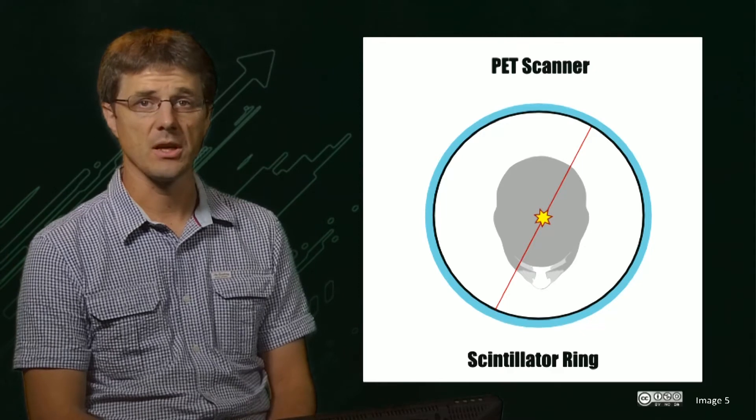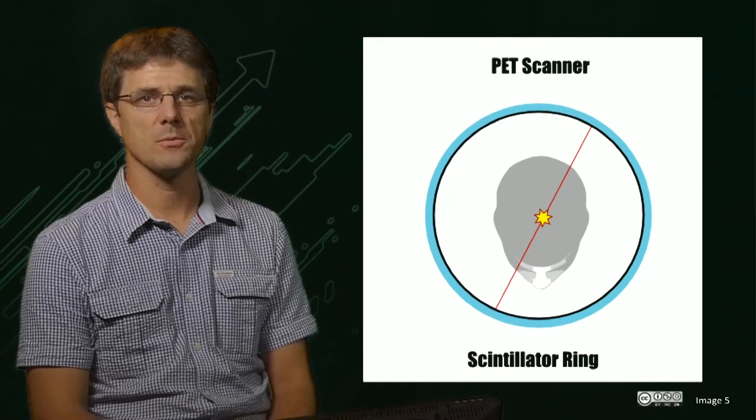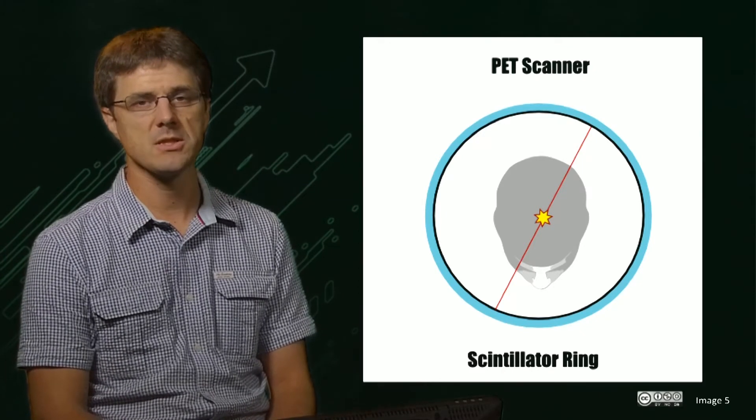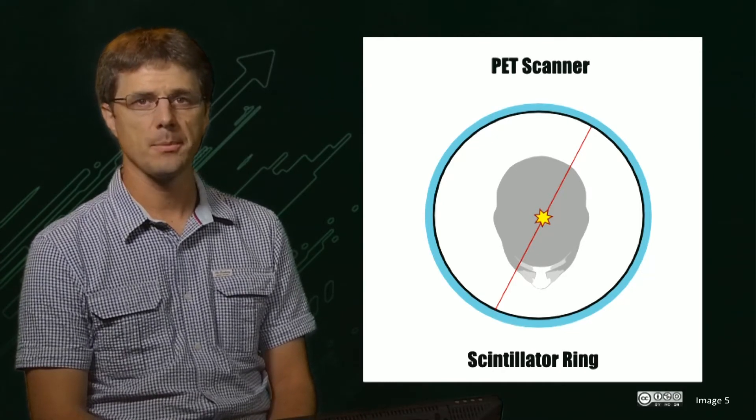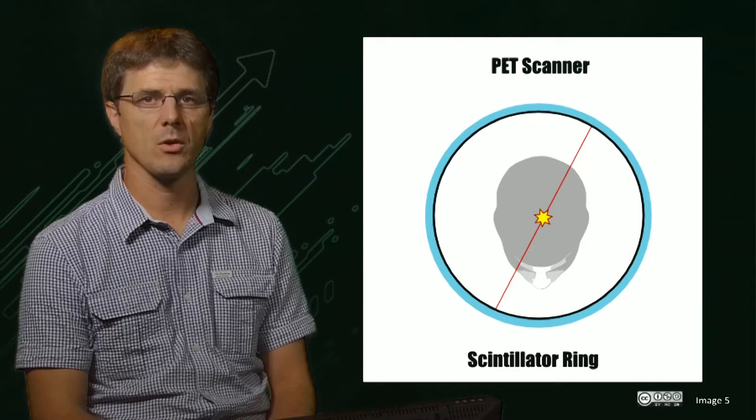Given their velocity, irrespective of their location in the object, these two photons will hit the detector ring at essentially the same time. When this happens, the scanner records what is called a coincidence event.